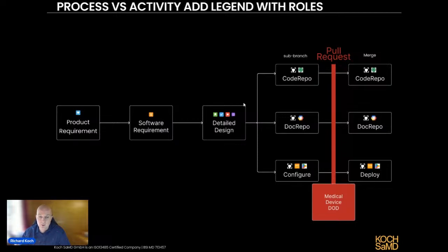I look at the procedure, what they do, compare it to the standards and say, look, is it compliant or not? Now, from a code perspective, before I do that, I'll try and explain this procedure. It's basically the design V up until deployment without the testing and verification. We've got Jira. This is how I configure my Jira board. We've got a product requirement ticket, which causes a software requirement ticket, which causes a detailed design ticket. And I've got various ticket types on there.